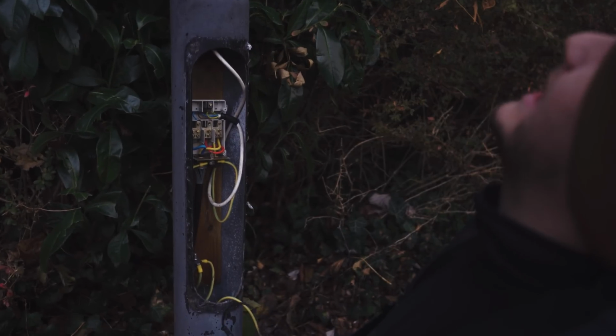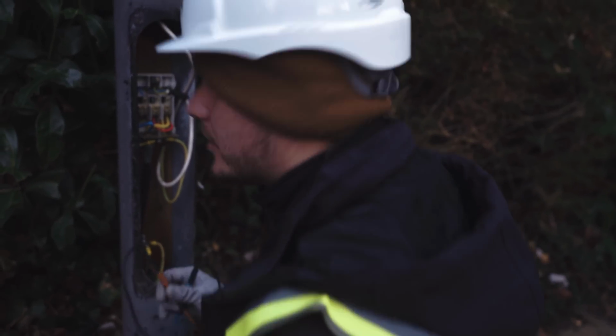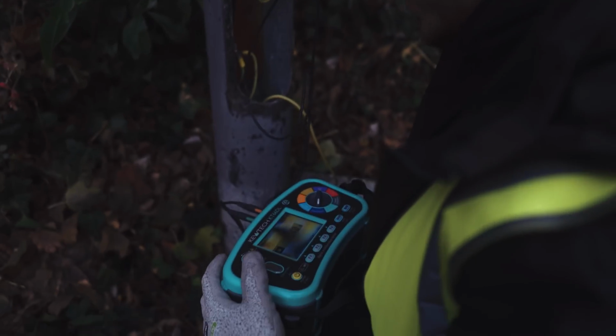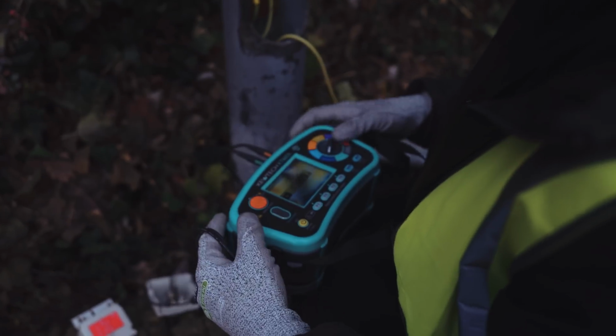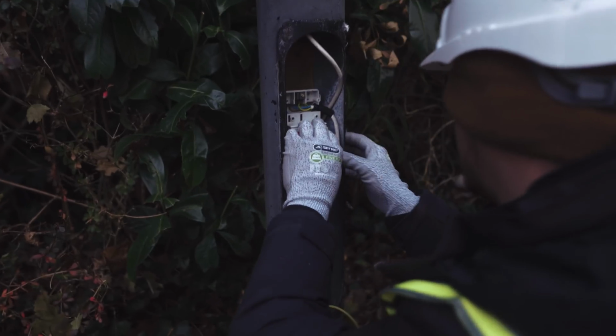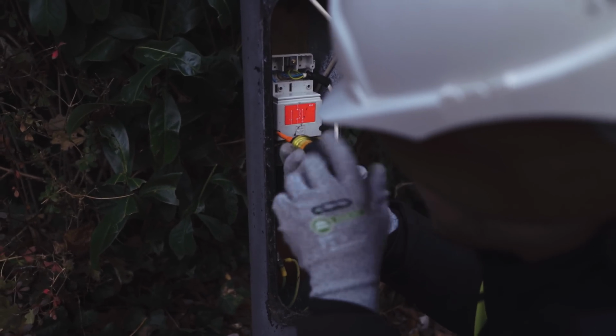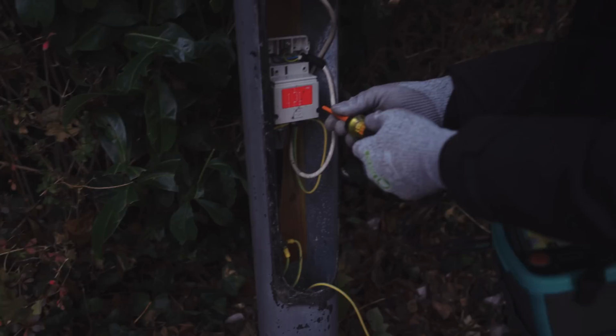I mean, if they're going all LED, that's quite a possibility. Might be able to drop down to a 10 amp, which obviously gives you a higher tolerance. But yeah, at the minute that's not fluctuating, that's sitting bang on 1.4. So yeah, that would have failed me, old mucker, but obviously it's all coming out now anyway. But yeah, it's quite important with validations.